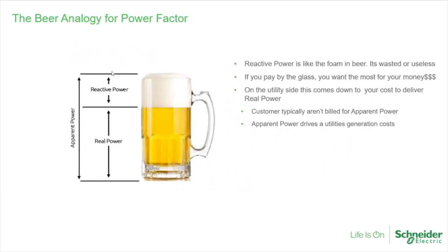And then this is an analogy that a lot of people usually like: the beer analogy for power factor. Reactive power is like the foam in beer. It's wasted or useless. And if you pay by the glass, you want the most for your money. The real power is the actual liquid. But when you buy the glass, you're not getting a full glass of beer. In this example, it looks about like two-thirds. So on the utility side, this comes down to your cost to deliver real power. Customers typically aren't billed for apparent power. They may have a kVA peak demand, but apparent power drives your generation costs because that's the demand on the system.